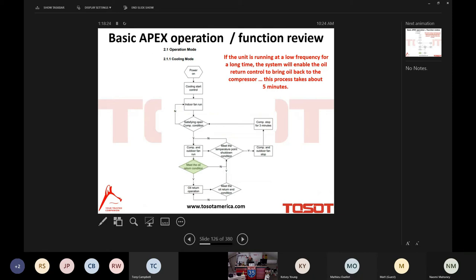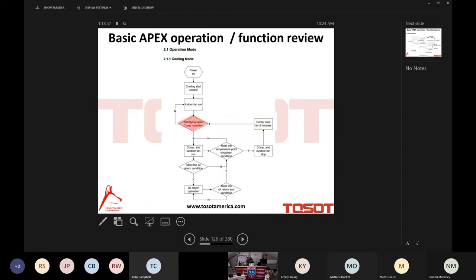if it's been running at low frequency, it's going to go into this oil return process. That operation will take place. The oil will return after about 5 minutes. And now we have met the set point temperature and the system starts to power down. The compressor and the outdoor fan are going to stop. And then the compressor will stop for a minimum of 3 minutes before we start the compressor again for the next active call for cooling.